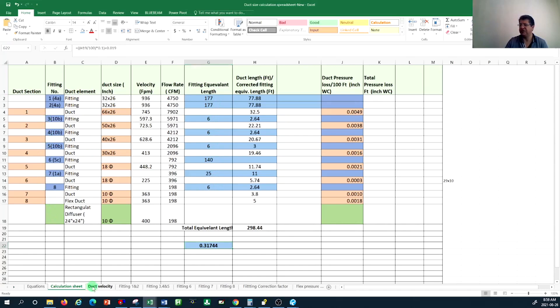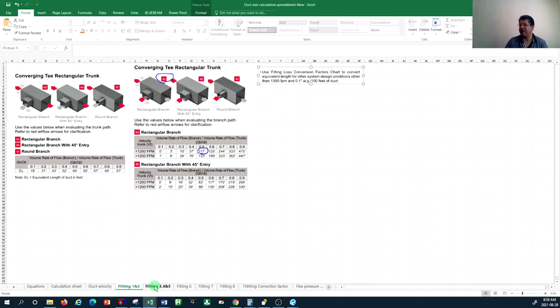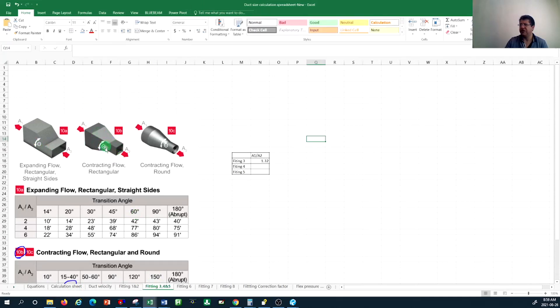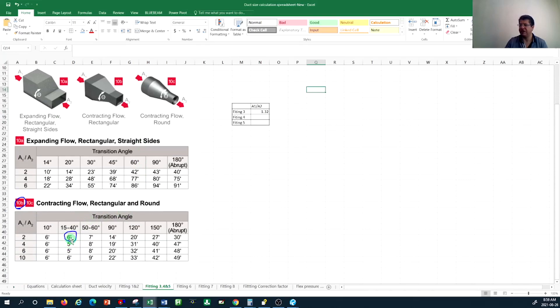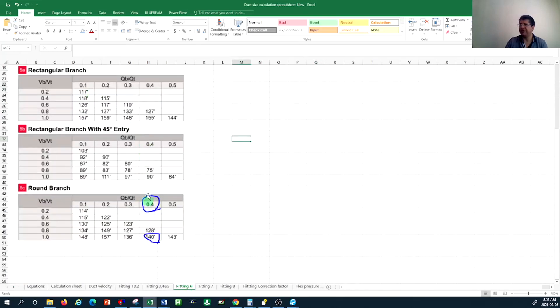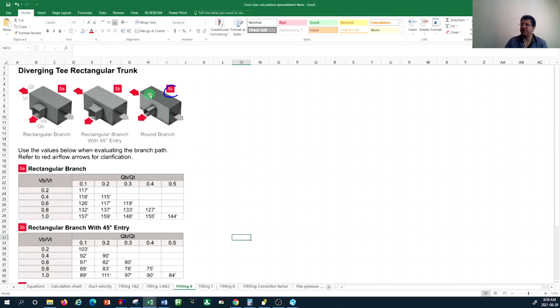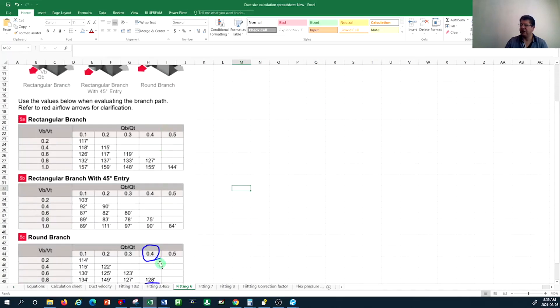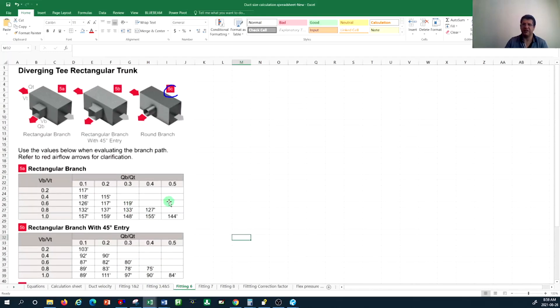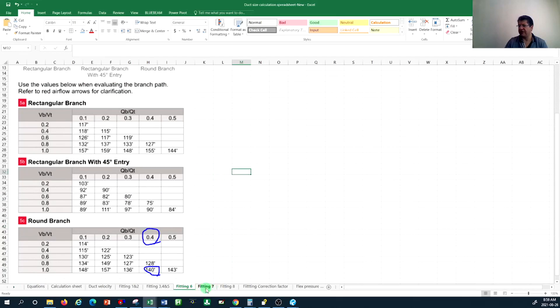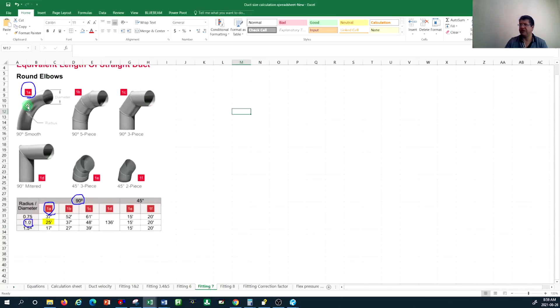I continue that with all other fittings. Fitting number three is fitting type 10B — a transition on the rectangular duct — and we calculate the equivalent length. Fitting number six is a transition from rectangular to round duct, so I get that from the relevant table. This would be very extensive to go through in detail for every fitting.